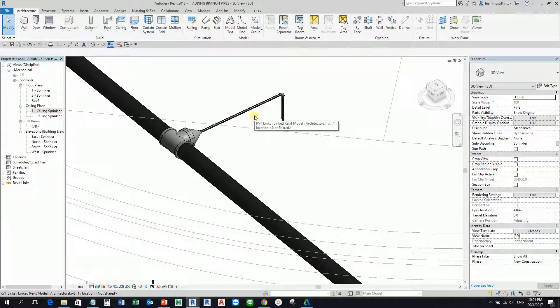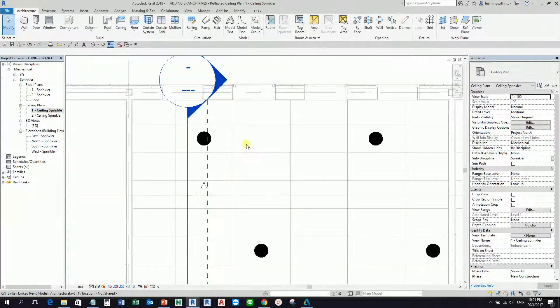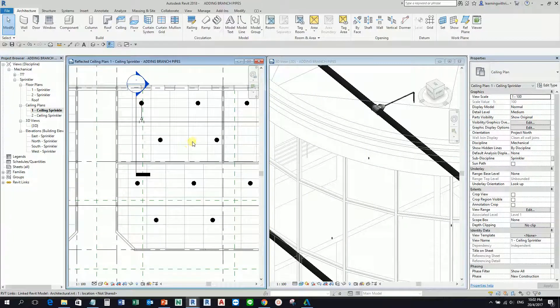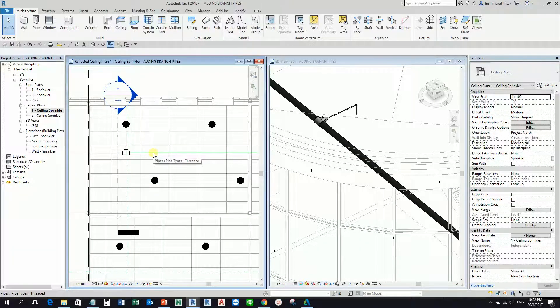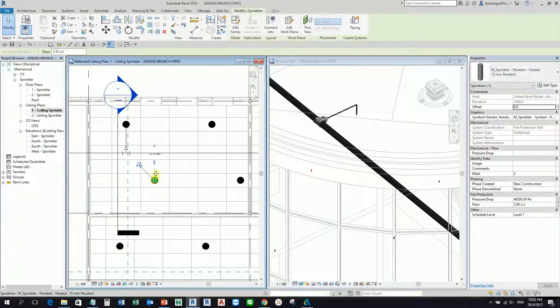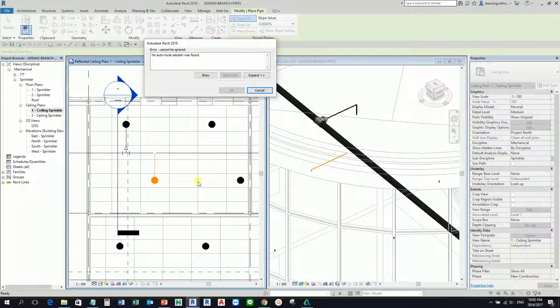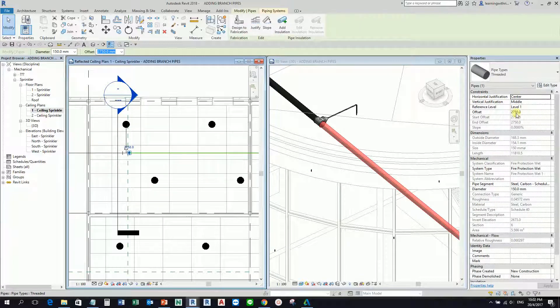I'm just showing you how to connect your sprinklers to the pipe. Let me open my ceiling plan — type WT for Windows Tile — so I can see the floor plan as well as the 3D view. Now another option: if I try to connect this sprinkler to the pipe directly, there's an error because the height of my sprinkler is too close to the main pipe — the sprinkler is at about 2,400 mm and my main pipe is at about 2,700 mm, a difference of only 300 mm.